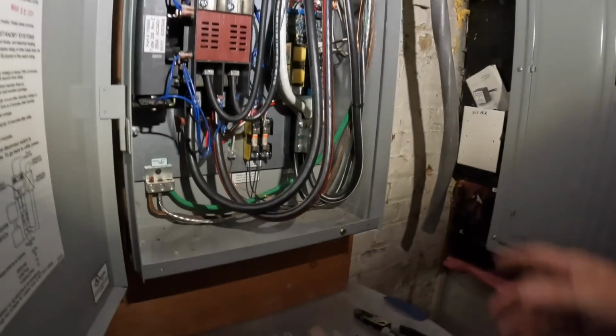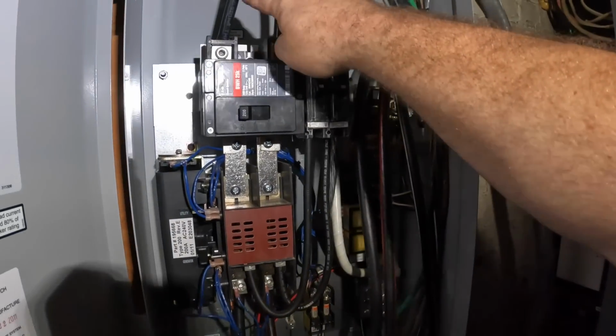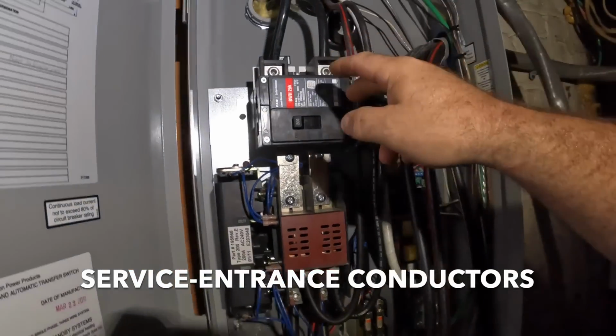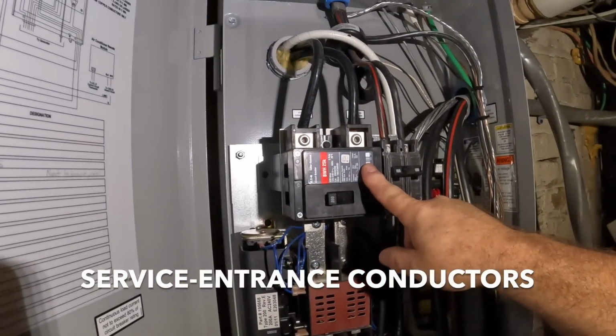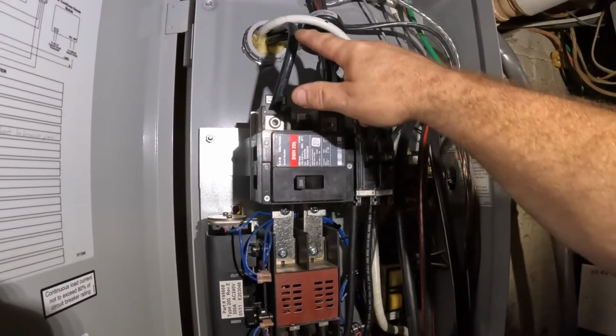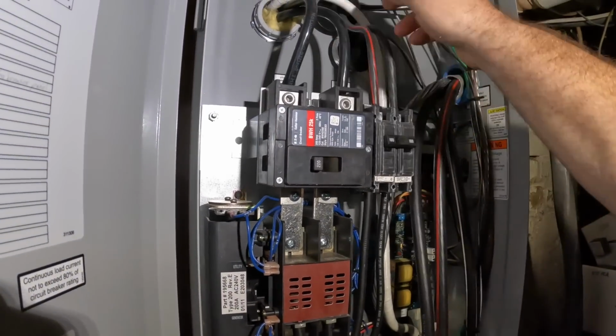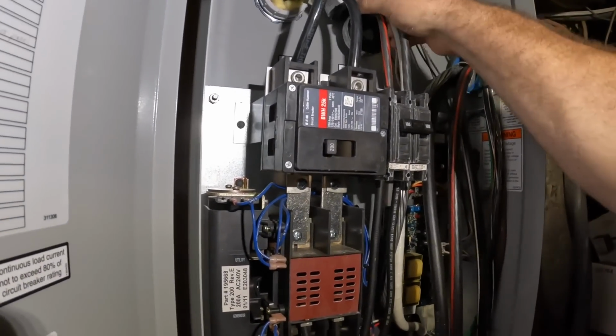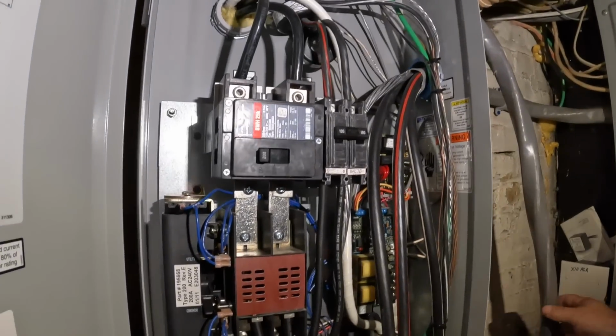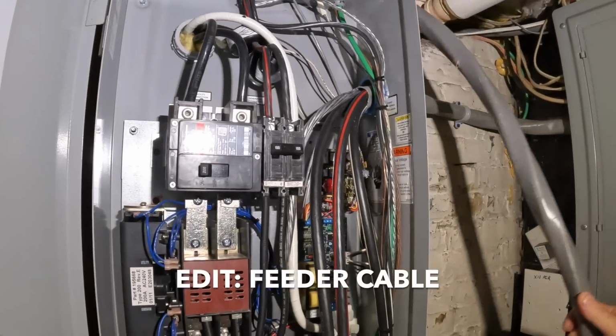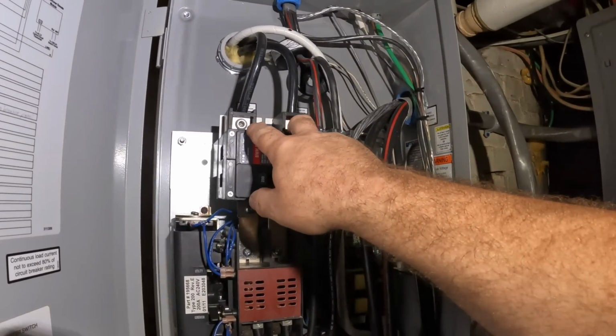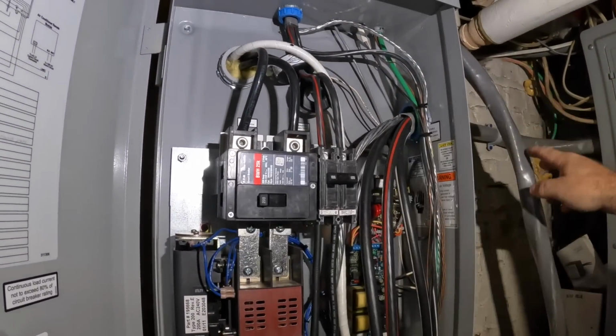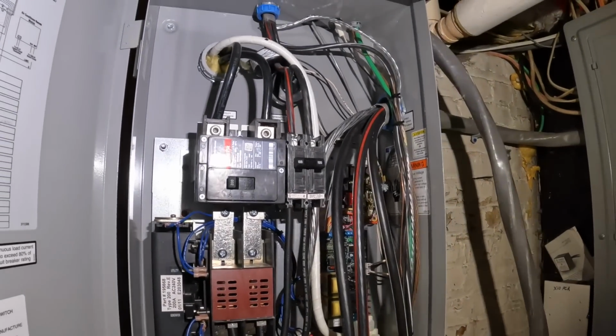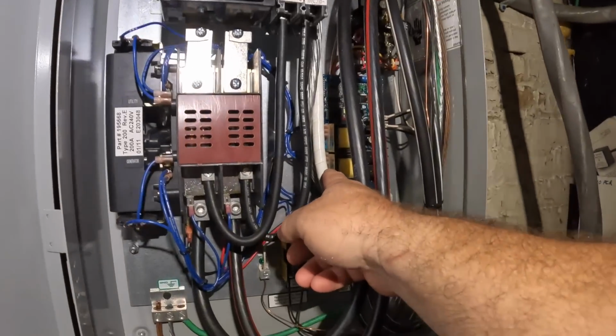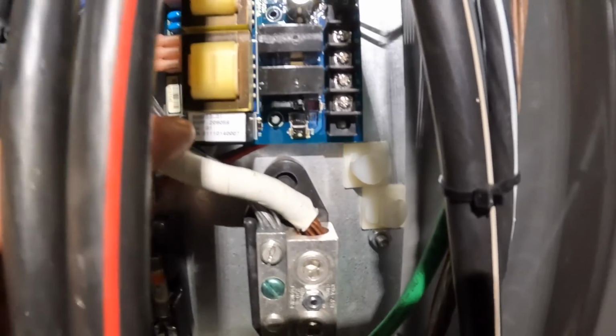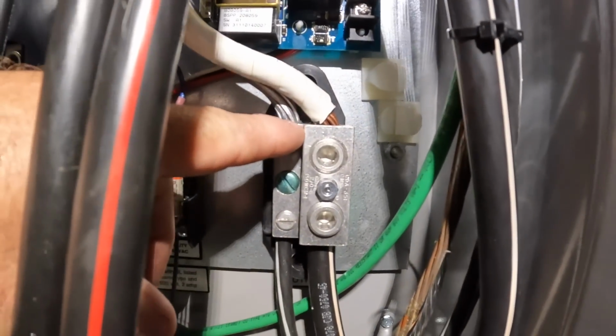Right here are what's known as my service entrance conductors. They come into this main breaker, which is the automatic transfer switch. These are getting removed, and this too. In their place we're going to install this feeder cable. Two of the conductors will land on this main breaker, and the neutral will land where the previous service entrance conductor was landed, in this terminal for the neutral.